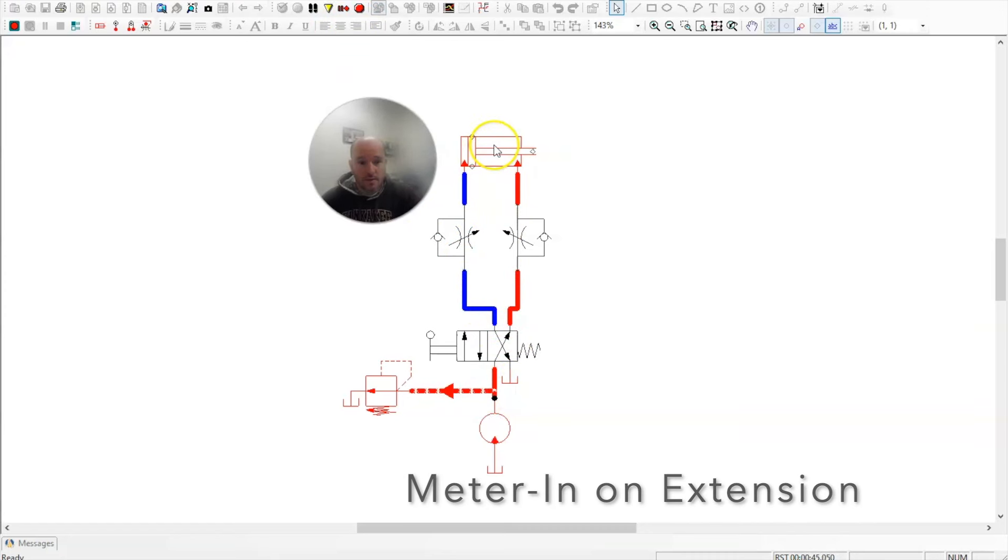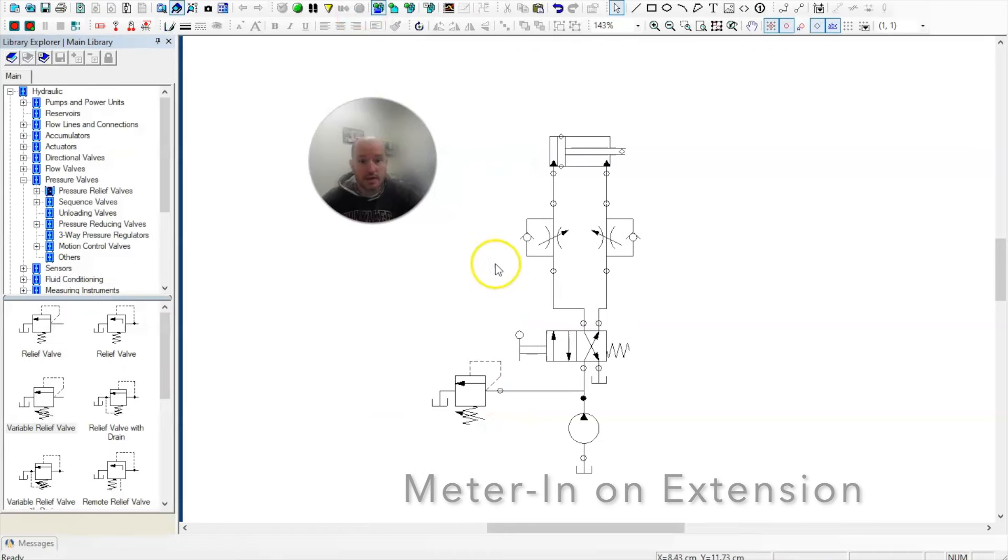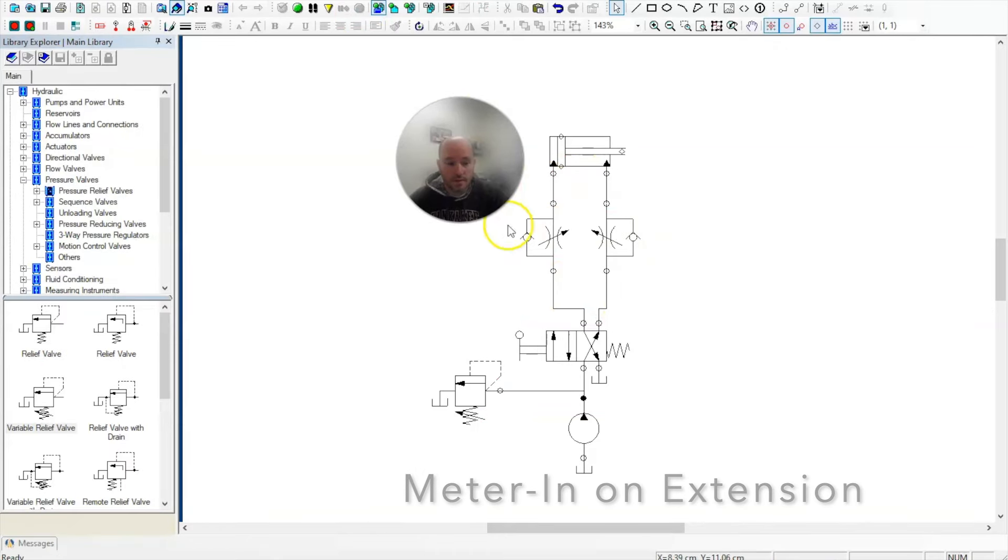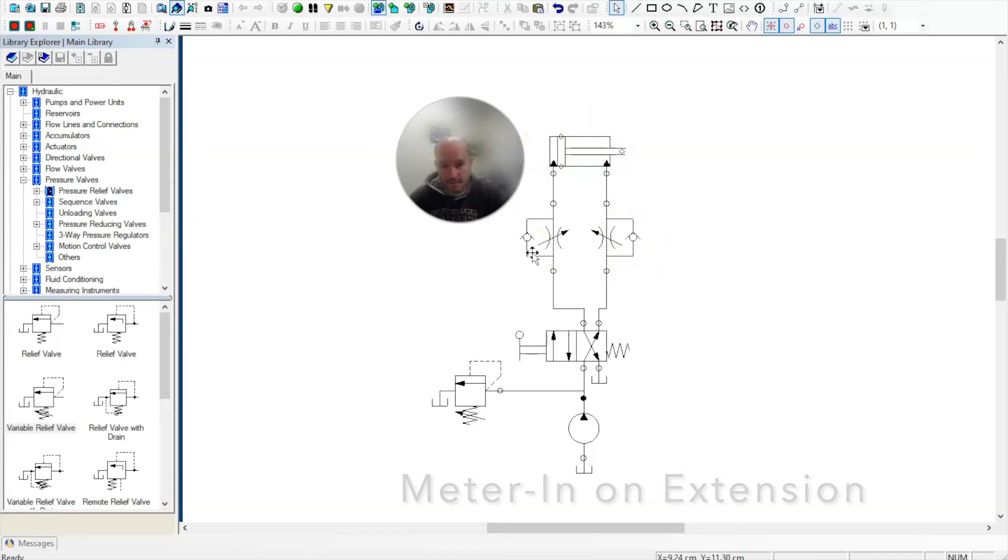This is how you control the speed of a double-acting cylinder in both directions using a meter-in circuit. What's important to notice is that the arrows are both pointing towards the cylinder. As soon as you see that, you know this is a meter-in circuit in both directions.